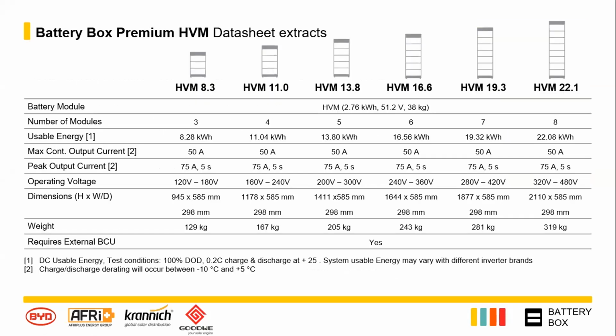I'd like to just explain a bit about how the BYD high-voltage batteries work, because they're not readily available in South Africa, and I'll just give a background on how they function. So here on the top, you can see the towers. It starts between 3 modules and 8 modules. And as you add each additional module, the amount of current you can get out stays the same, and the nominal voltage of your battery bank rises.